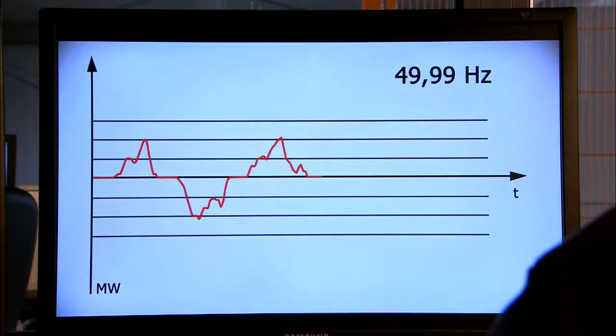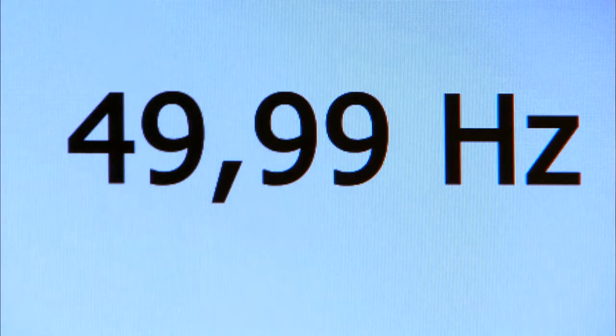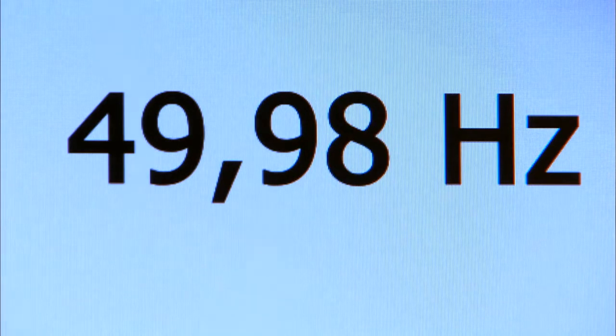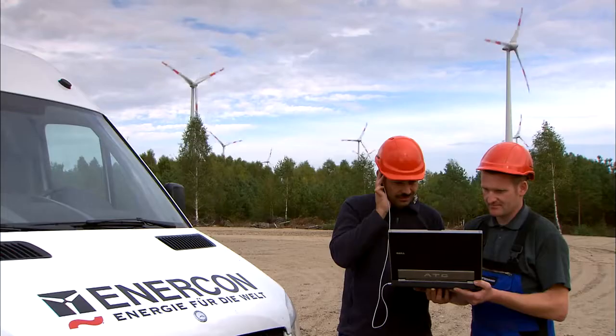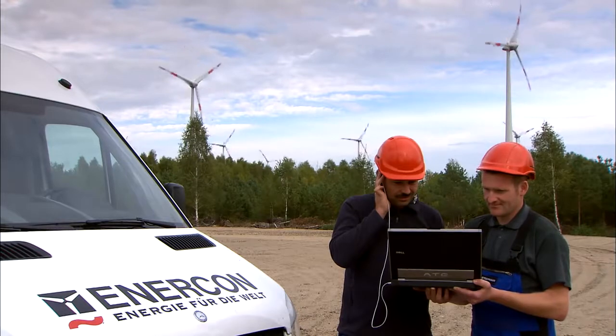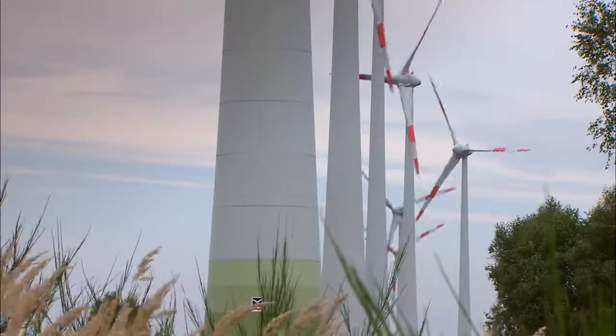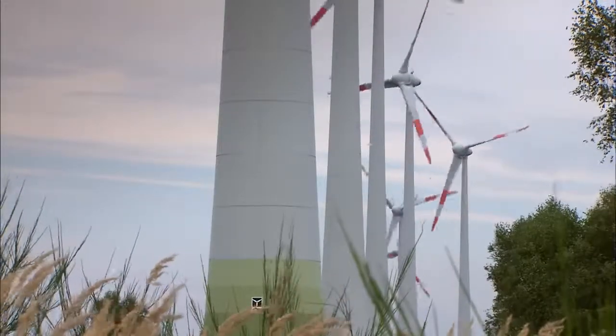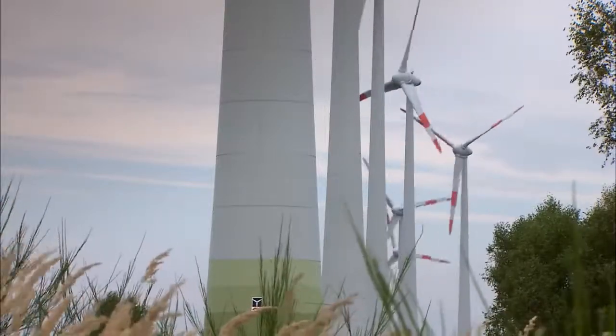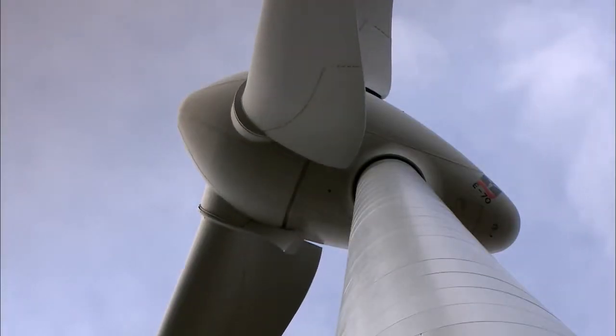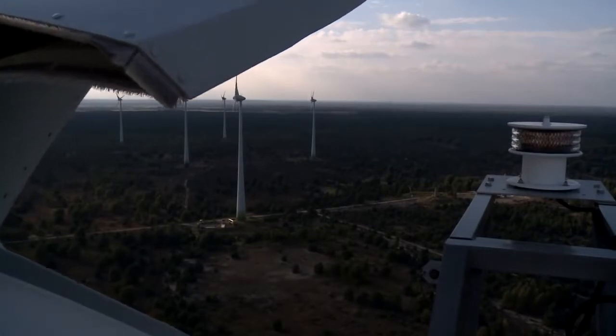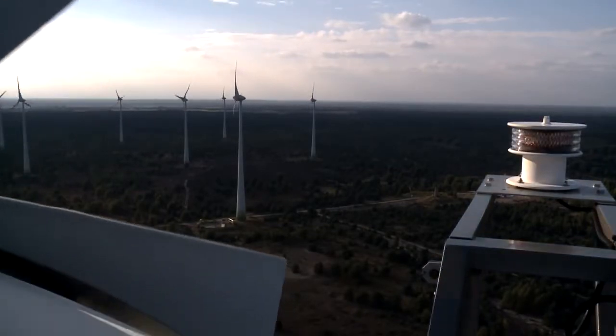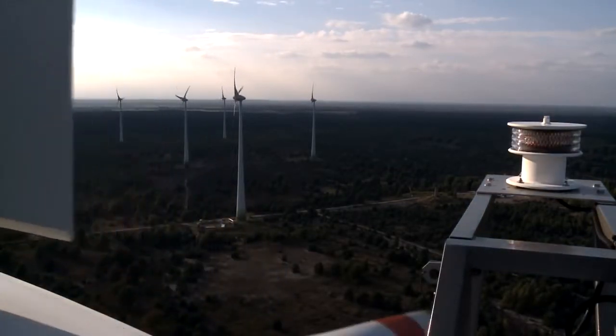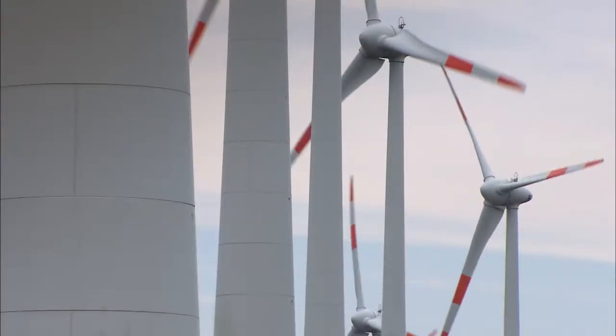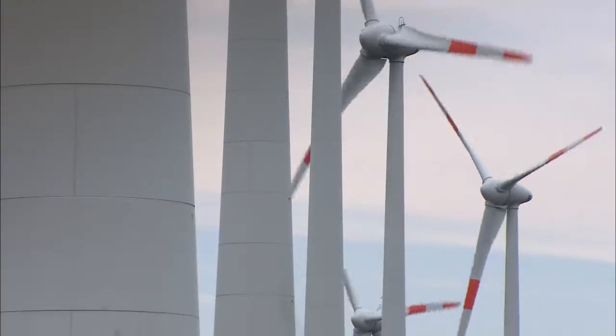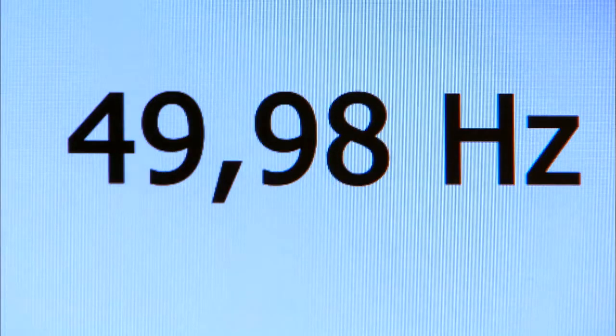At the same time, the frequency drops in the other experiment. That means more power is demanded than supplied to the grid. The wind farm in Brandenburg still has 4 megawatts of positive control reserve on hand. That means some plants are not running at full capacity. The blade angle is altered. The turbines rotate faster. And the frequency rises.